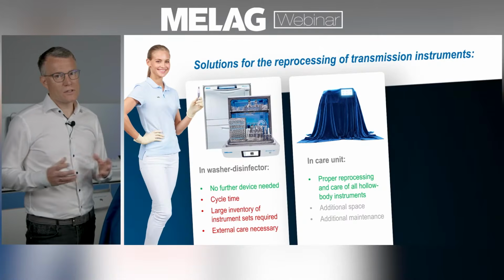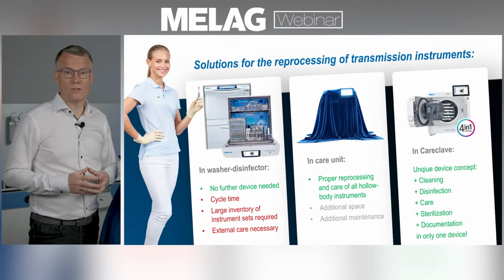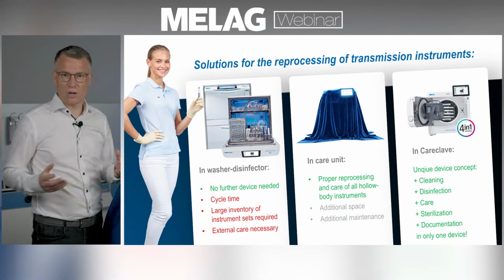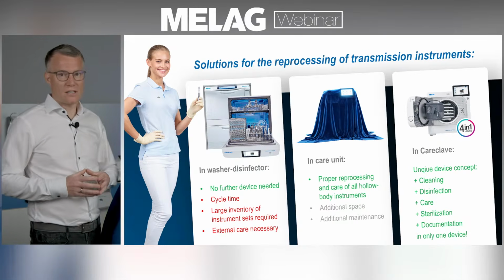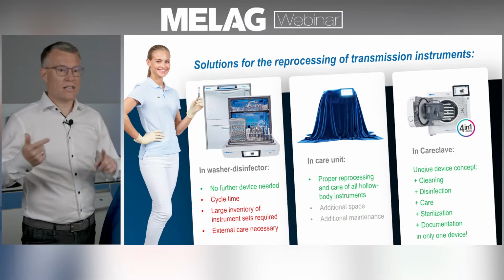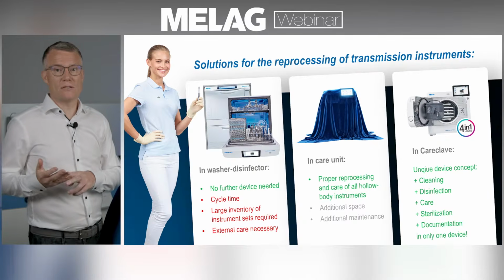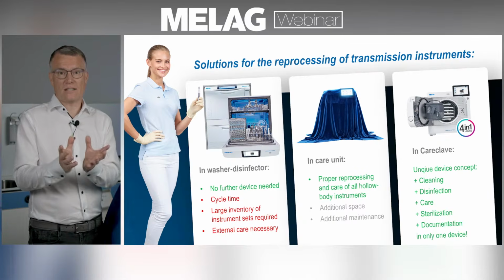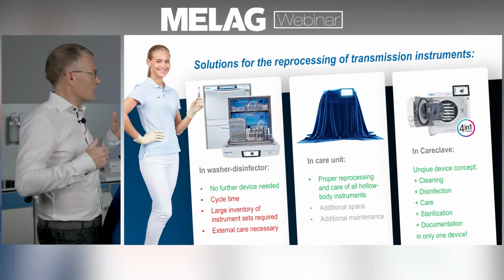There's actually one solution left, which is a 4-in-1 or all-in-one solution. There's a device called CareClave, a unique solution that combines everything we've talked about: cleaning, disinfection, care, oiling, sterilization, documentation and approval in one device. It offers time, space and service cost advantages. However, from many discussions with dental practices and clinics, we've found there is still demand for a standalone lubrication unit, because a practice may have already invested in a Class B sterilizer 1, 2, or 4 years ago.